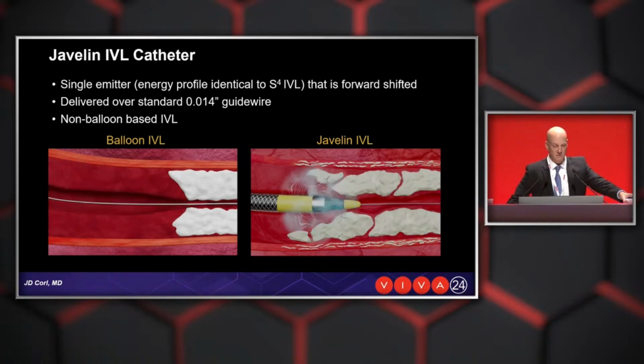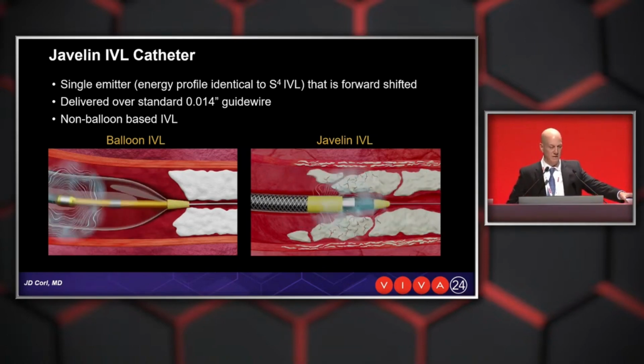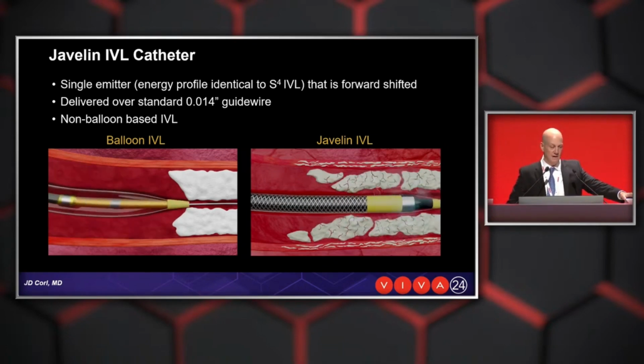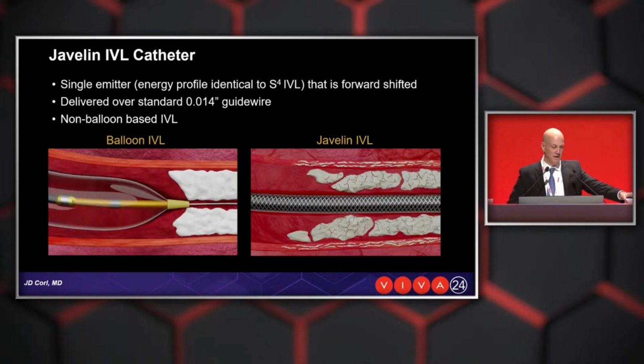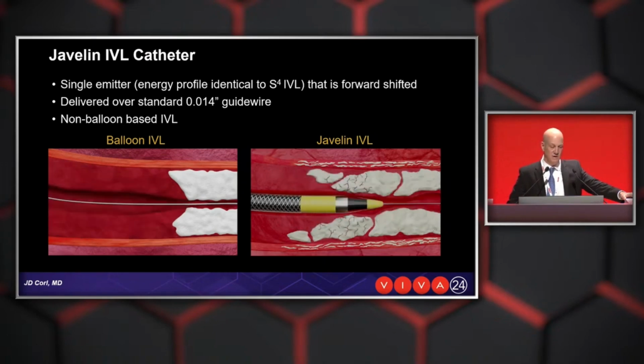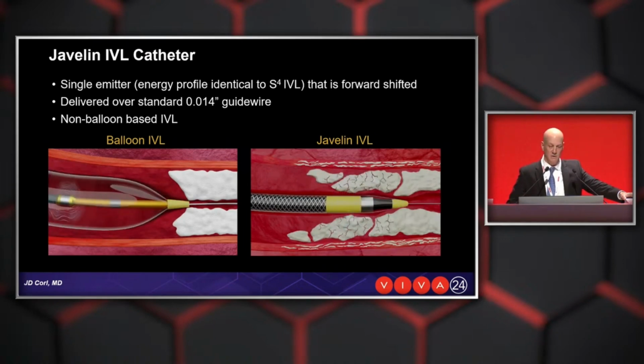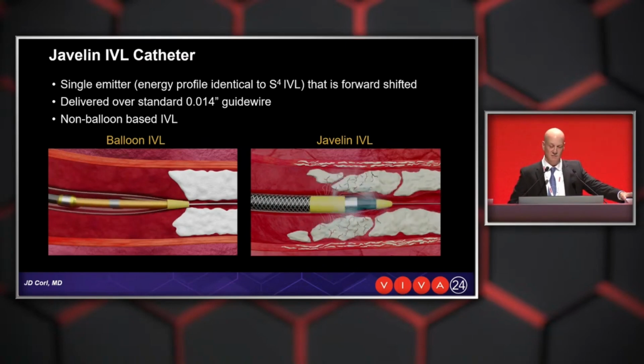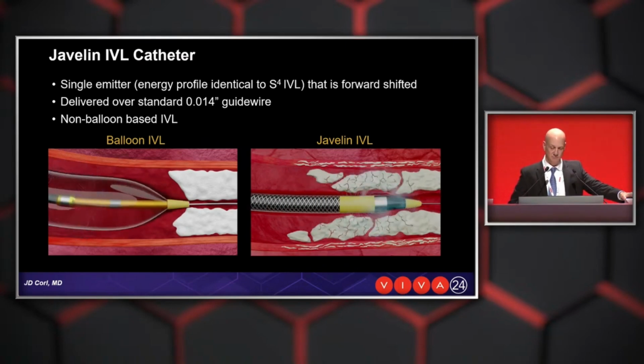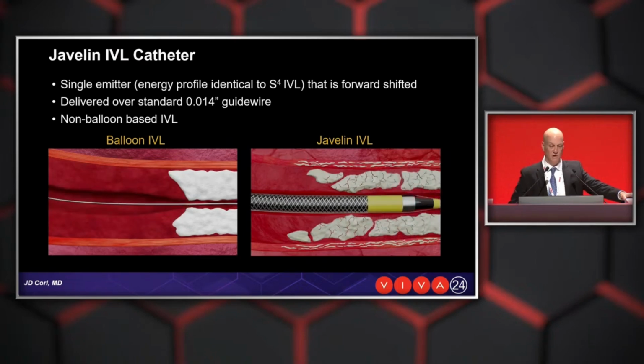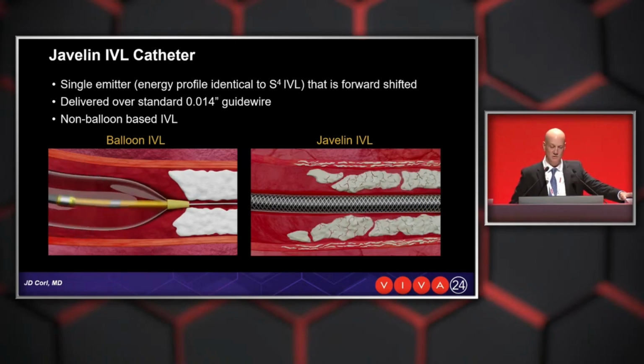On the left side, you can see our standard balloon IVL, where the tip is too far from that distal emitter to effectively treat the cap or that calcium at the tip with the pulse. You can see the radius of that pulse does not effectively reach the tip of that catheter. With the Javelin catheter, you can see that emitter is shifted forward approximately 3 millimeters from the tip, and that pulse does extend beyond the tip, so it can effectively treat and modify that calcium and allow for the catheter to cross. You can also see as the catheter crosses, it does modify that calcium in the process.